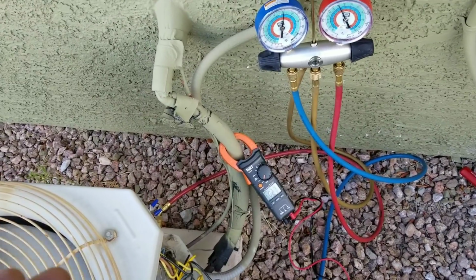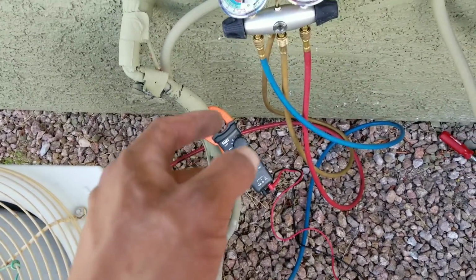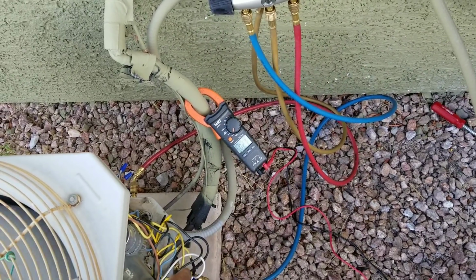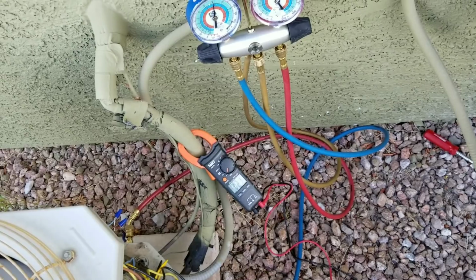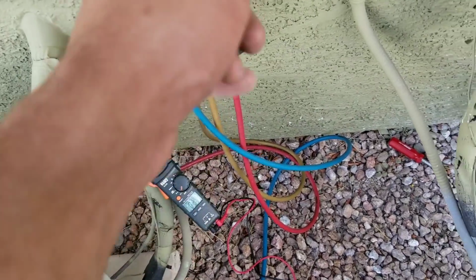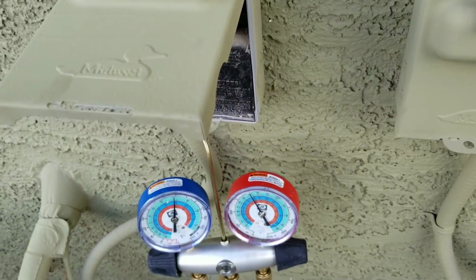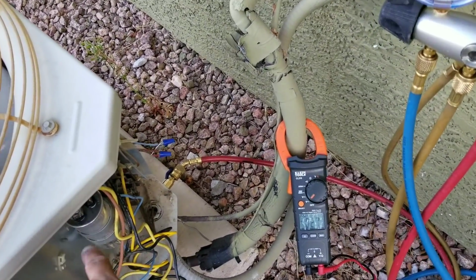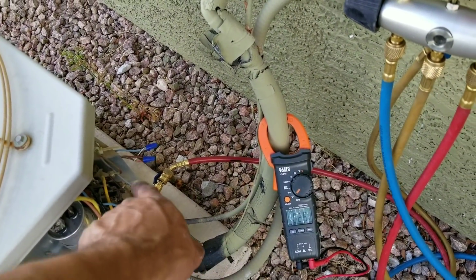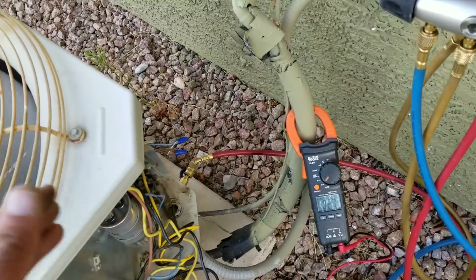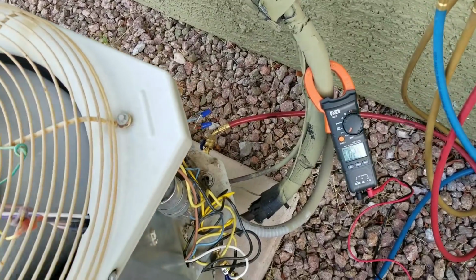I always repeat the same process to my guys. When you come, make sure you have your multimeter, make sure you have your gauges. Plug your gauges in. That will tell you if you have refrigerant in the system. Come over here, make sure that your disconnect is in. Open up your panel, check the low voltage, check the high voltage, and then from there you'll be able to isolate where the problem is.